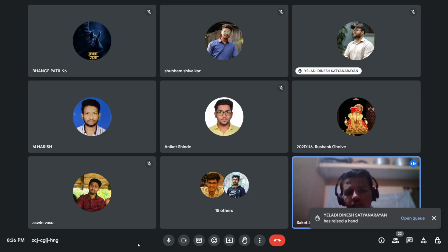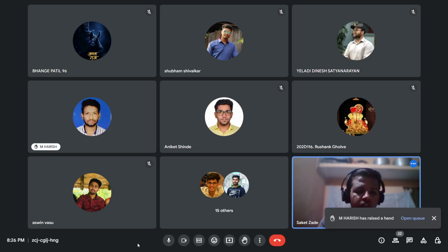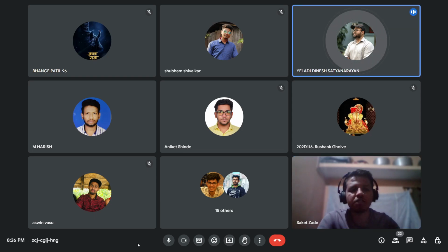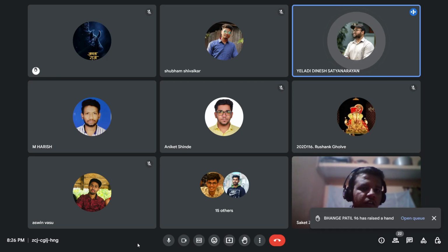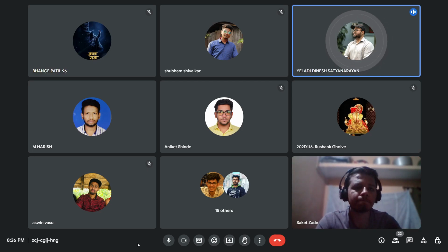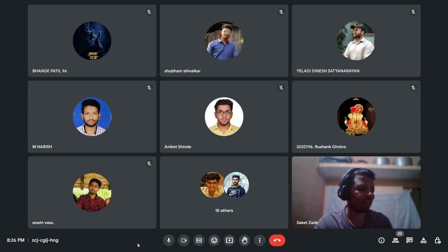Okay, Dinesh, you can tell. Everybody speak up, guys. The VCR safeties are low oil pressure cutout, high pressure cutout, low pressure cutout. Then we have oil heaters, and also we have a relief valve, solenoid valve, master solenoid valve. Yeah, that's it. Okay, that's correct.